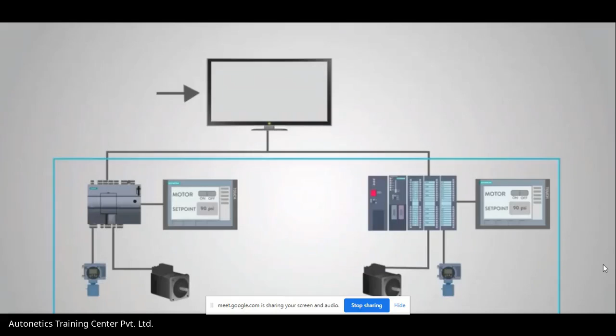SCADA systems are used for monitoring and controlling large areas, typically a full site or plant. SCADA systems are a combination of many systems including sensors, RTUs or remote terminal units, and PLCs. Data from all of these systems is then sent to the central SCADA unit. That SCADA unit has its own HMI, which is why a lot of people get confused and think SCADA and HMI are one and the same. That HMI, or human machine interface unit, on the SCADA can monitor and control anything connected to it. In conclusion, HMI can be a part of a SCADA, but SCADA cannot be a part of HMI. It's that simple.